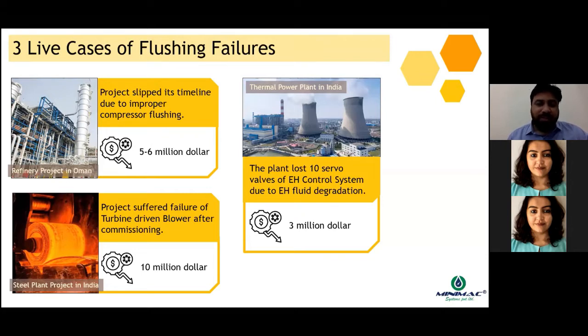The third project is a thermal power plant from India. This thermal power plant has an EH control system. The EH control system is for the purpose of governing the steam turbine. Due to the EH fluid degradation, there were a lot of stuck-up problems for the servo valves. Because of sludge, because of varnish in the system, the valves were not operating freely. Due to this, the plant went on an outage, and there were at least 10 servo valve failures recorded during a span of just 10 months. The total impact on the project was around $3 million.